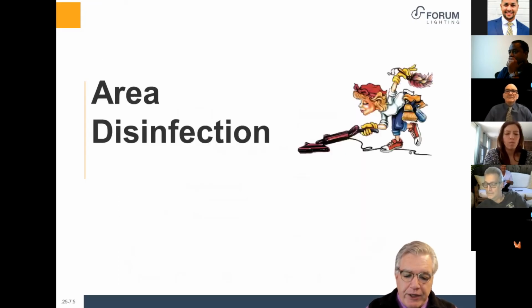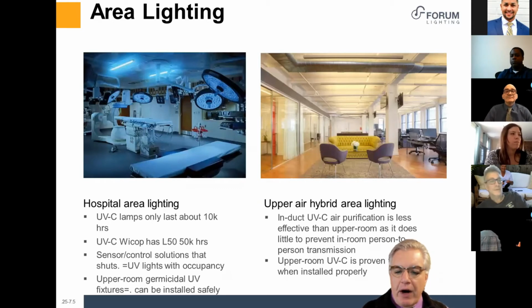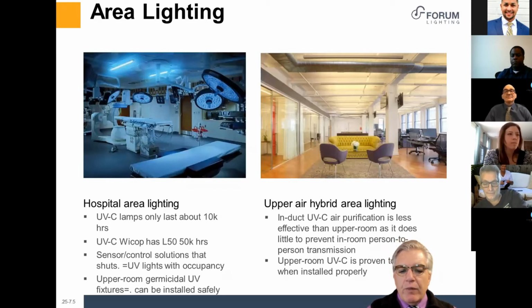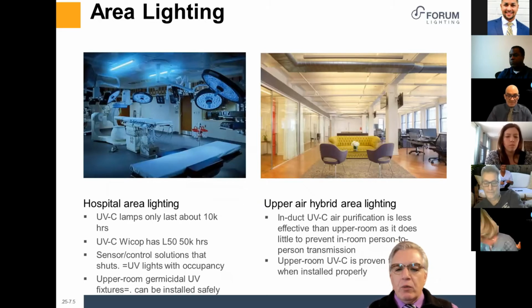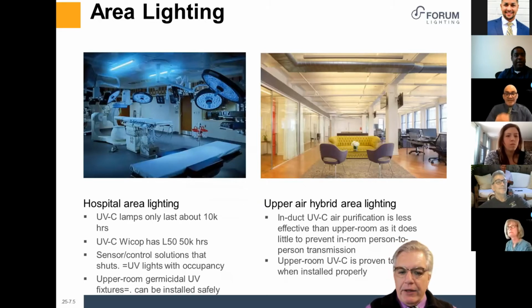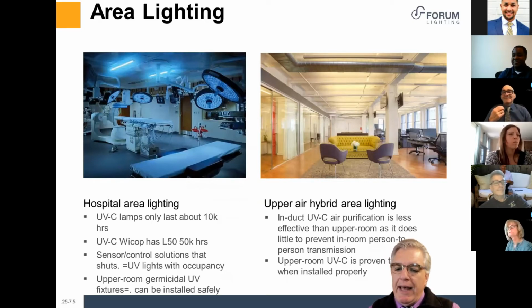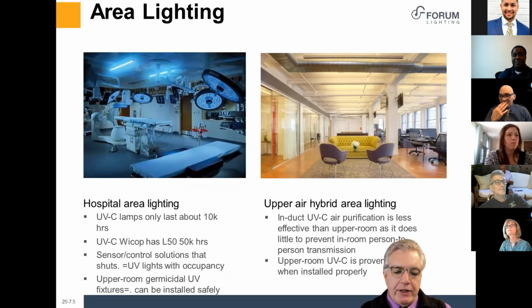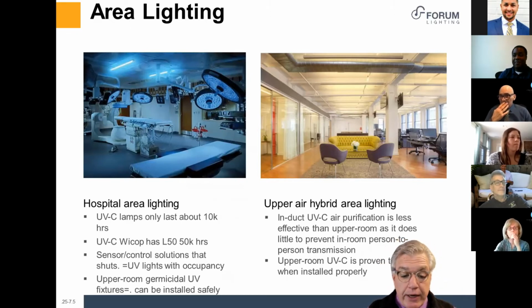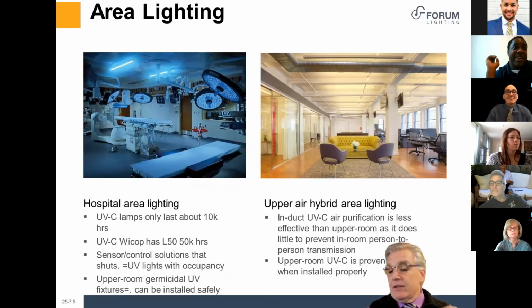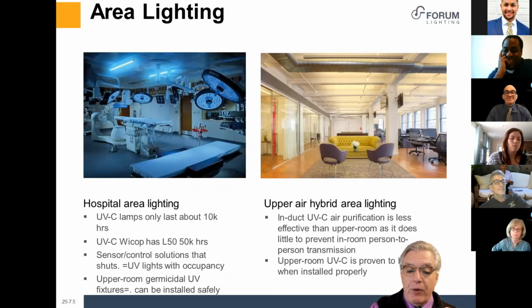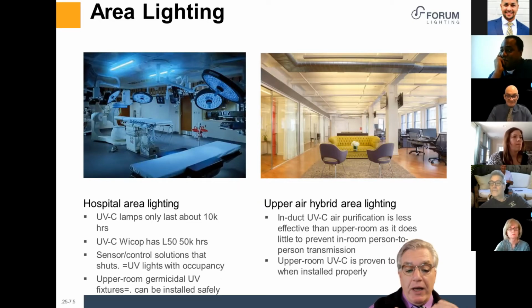So area disinfection. How do we get this into the environment or into the space? Not the only two, but two typical strategies are a direct installation of UV sterilization, or an indirect UV sterilization strategy. In a direct UV sterilization strategy, as you can see in the picture, we lock down the space, we have occupancy sensors, and we have redundancy to make sure that if a person steps into the space, it'll turn the fixtures off or not let them in the space at all.